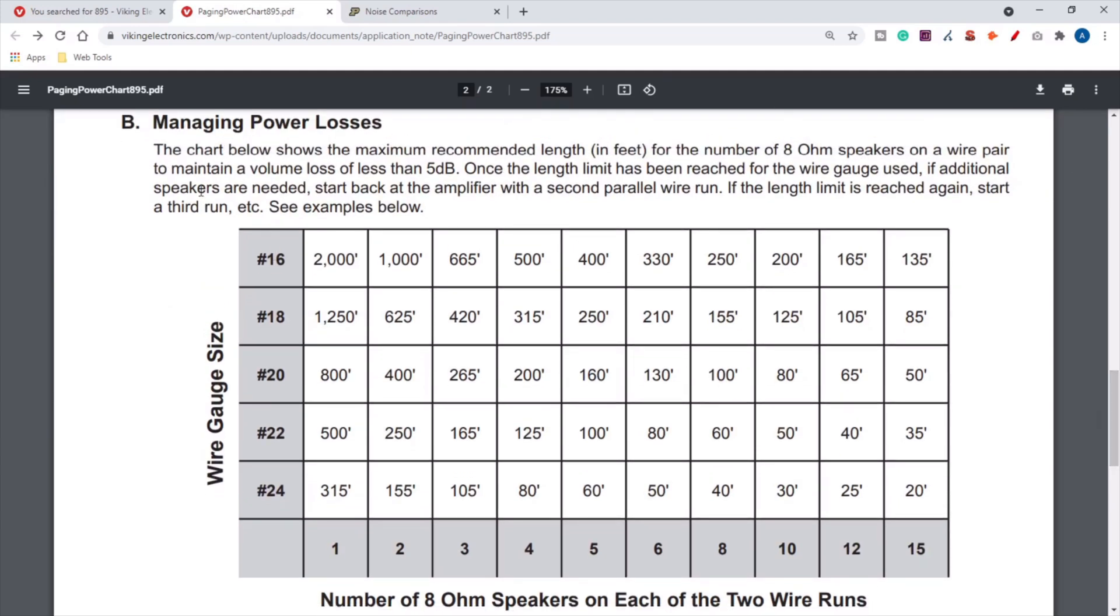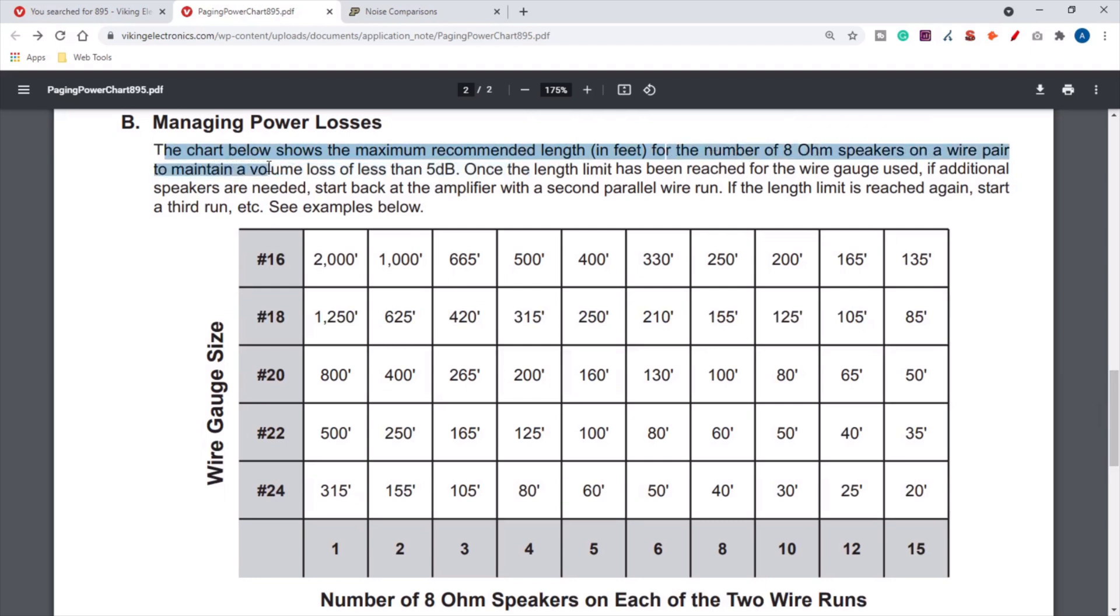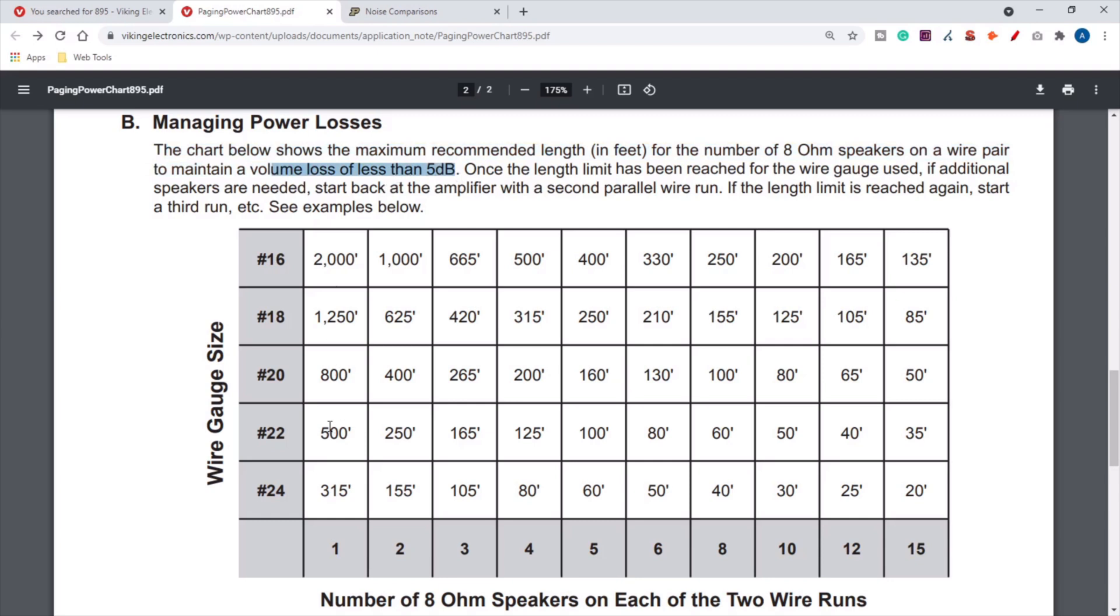The chart below shows the maximum recommended length in feet for the number of 8-ohm speakers on a wire pair to maintain a volume loss of less than five decibels. That should be a perceived volume loss of less than five decibels at the furthest speaker. This chart is giving you your wire gauge size compared to the number of 8-ohm speakers on each of the two wire runs.